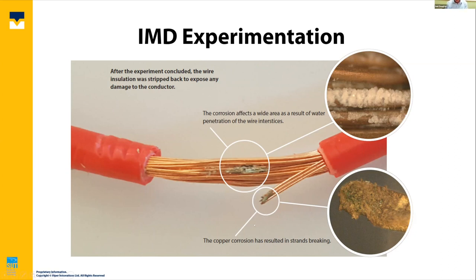One is the strands. We've got some broken strands here, and those have not been broken as a result of us stripping the wire back. You can see if we blow up what's happened, you can see the copper corrosion, and that the corrosion has actually eaten through the strand. And then the other thing we're seeing is some salt, which is obviously what's happened. Water has gone in through that hole into the interstices of the wire, and then when the wire's dried out, we've ended up with salt.